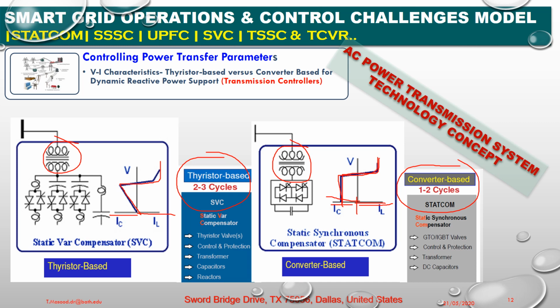Okay. The STATCOM is therefore superior to the SVC in providing voltage support under large system disturbances, during which the voltage excursion would be well outside of the linear operating range of the compensator. The capability of providing maximum compensating current at reduced system voltage enables the STATCOM to perform, in a variety of applications, the same dynamic compensation as the SVC with considerably higher rating. So that is very important, that we need to understand that the STATCOM is a more versatile compensator compared to the SVC.